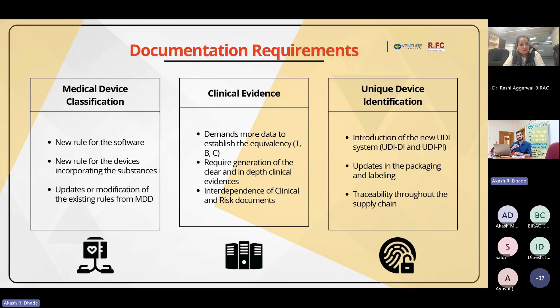Then there are requirements for unique device identification, UDI. As I mentioned, this can be a barcode which can be pasted on your device. It will give you information about the manufacturing date, manufacturing batches, then product information such as its description, the quantity and all those things. This is important in case your device fails in the market. You need to trace back what the batch was and whether that batch was manufactured correctly or not. If the adverse event is related to raw material quality, then you have to identify all the devices which went through that batch, and you have to recall all those batches. That is why this UDI requirement is very important. Then there is post-market surveillance.